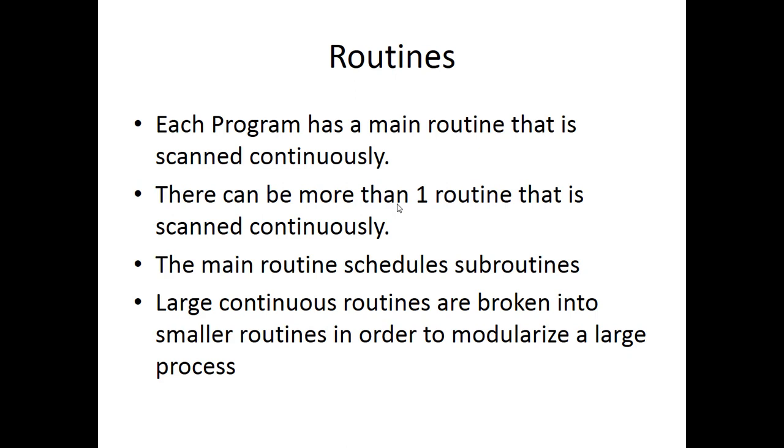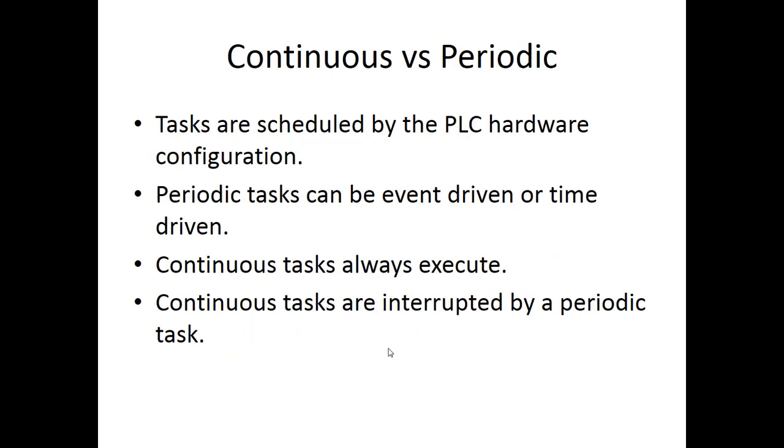So with routines, you have a main routine that's scanned continuously, and there can be more than one routine that's scanned continuously. The main routine schedules the subroutines, whether unconditionally or conditionally scheduled, and the subroutines contain all the ladder logic or FBD or ST, however you want to program them. Large continuous routines are broken into smaller routines in order to modularize and organize them.